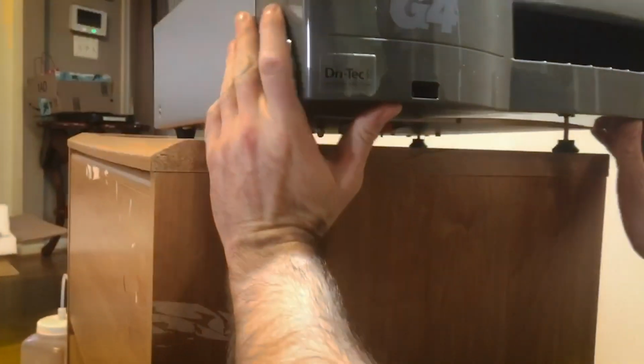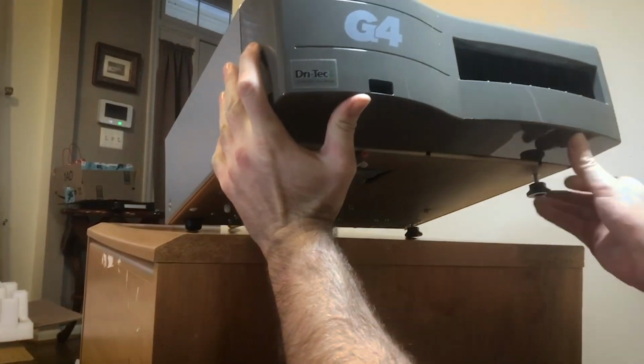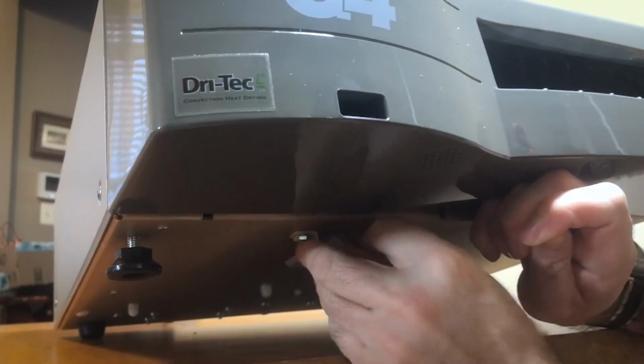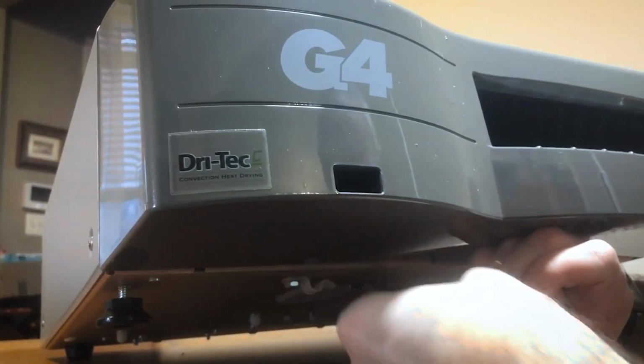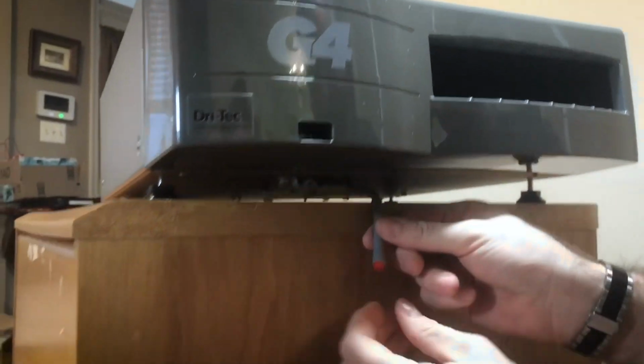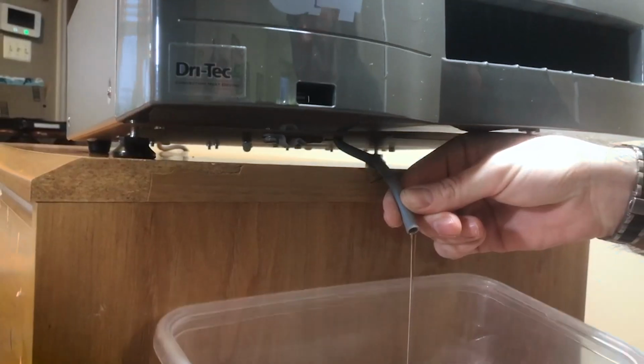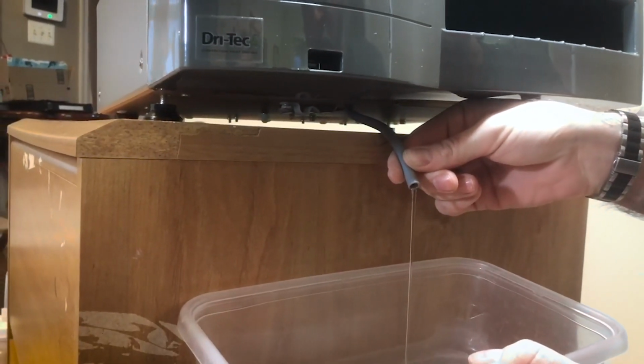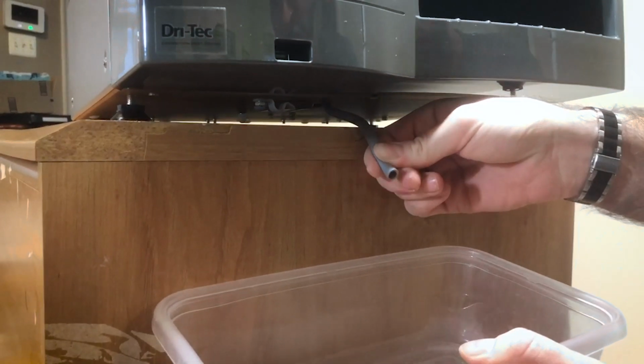Priming it is done by lifting the machine up at the edge of a table. There's a small hose underneath, and all we need to do is take the cork out of the end of that hose, hold it down for a little while, have something that we can drain some water in, and we want that water to drain for a good solid 30 seconds in order to make sure the machine is primed. And then we're ready to start our preparation cycles.